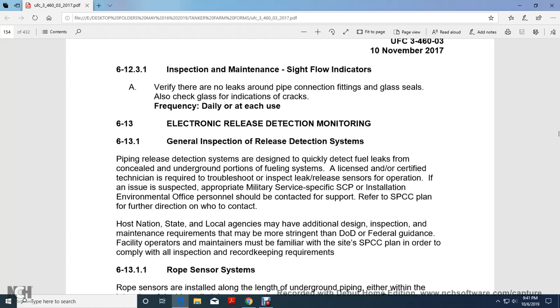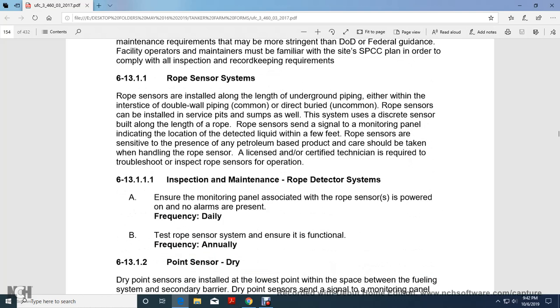Electronic release detection monitoring. 6.13.1 General inspection, release detection systems. Piping release detection systems are designed to quickly detect fuel leaks from concealed underground portions of the fueling system. Licensed or certified technicians are required to troubleshoot and inspect leak release sensors for operation. If a leak is suspected, the military service, spill prevention control point, installation environmental officer or personnel should be contacted for support. Refer to the spill prevention control countermeasure plan for direction on who to contact. Host nation, state and local agencies may have additional design, inspection and maintenance requirements that may be more stringent than the Department of Defense federal guidelines. Facility operations and maintenance personnel must be familiar with the site spill prevention control countermeasure plan in order to comply with inspection record keeping.